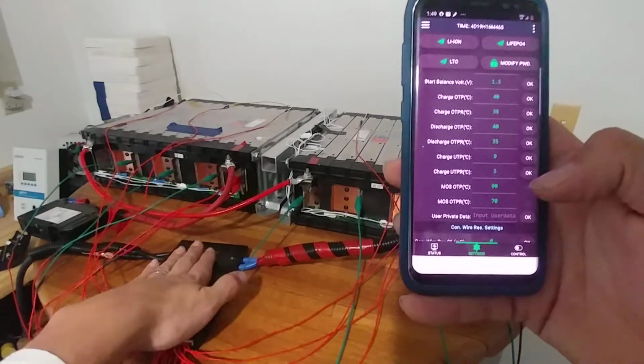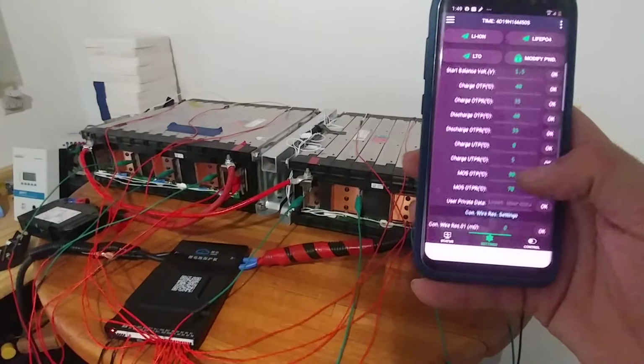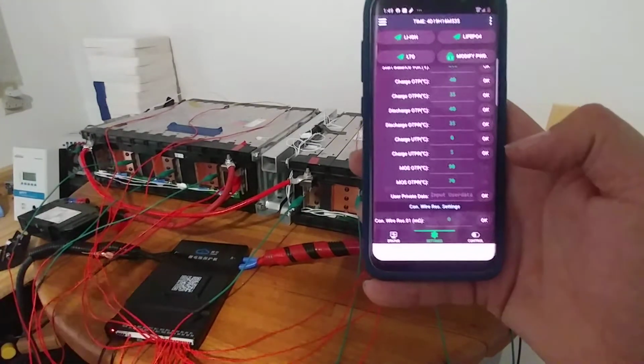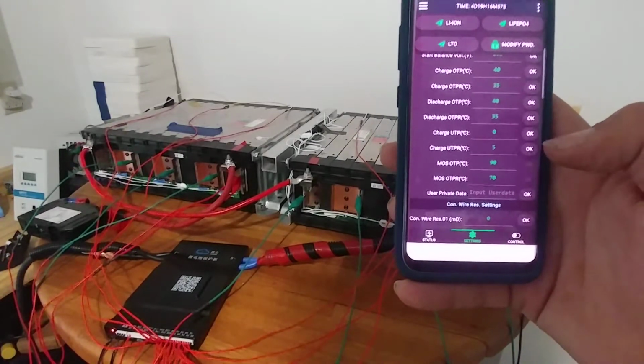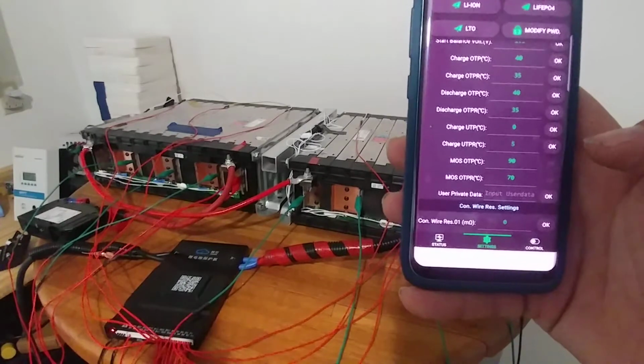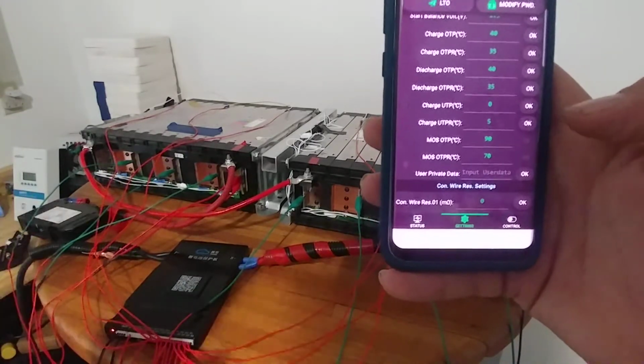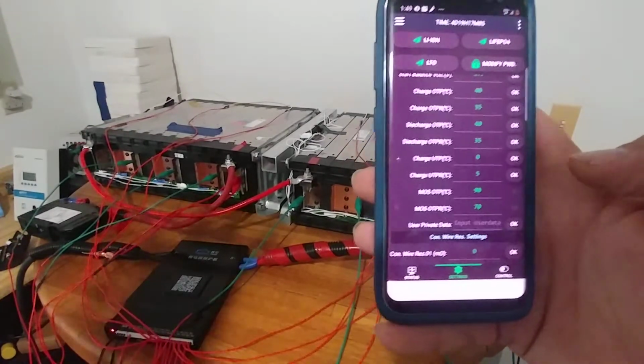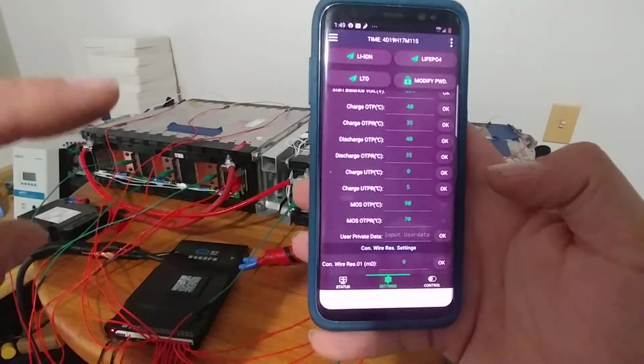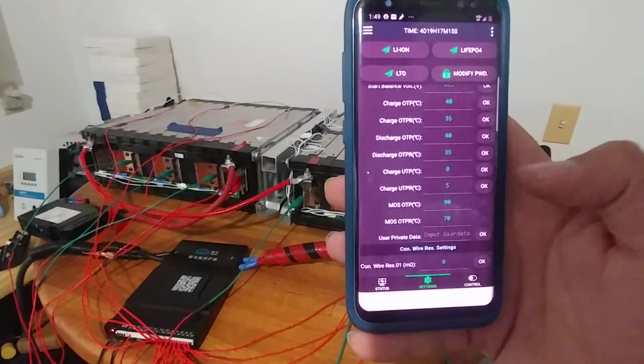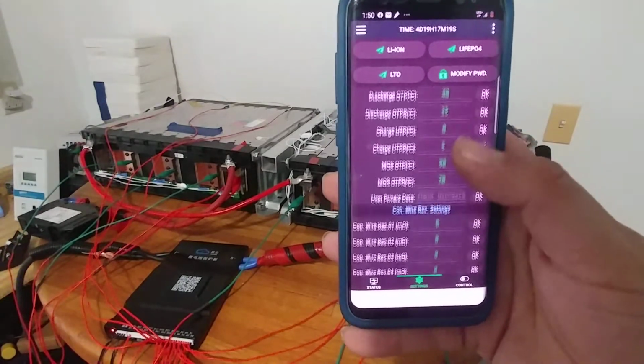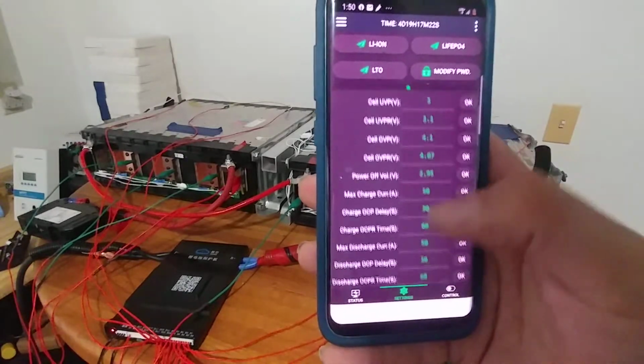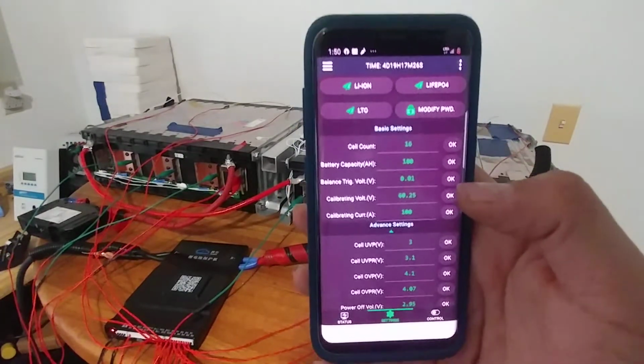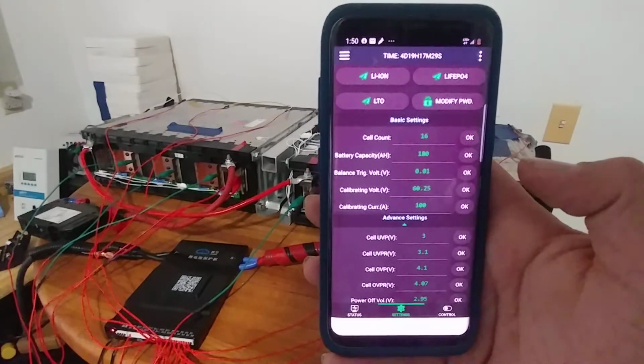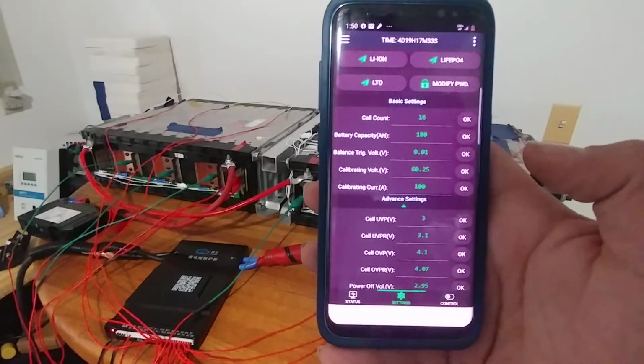And these two values are the over temperature protection for this unit itself, which has a default value of 90 and 70. I would probably lower that, or rather I'm going to lower that just for testing and monitoring, but you should actually determine how hot the batteries can get and what type of performance degradation you get, because certain batteries can handle higher temperatures and or lower temperatures, and you can adjust these values accordingly because this is a very flexible system. And that's about all the settings. There is no Coulomb counter, and it has been incredibly accurate so far.